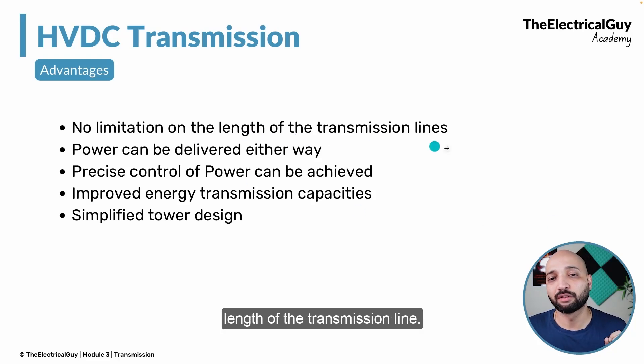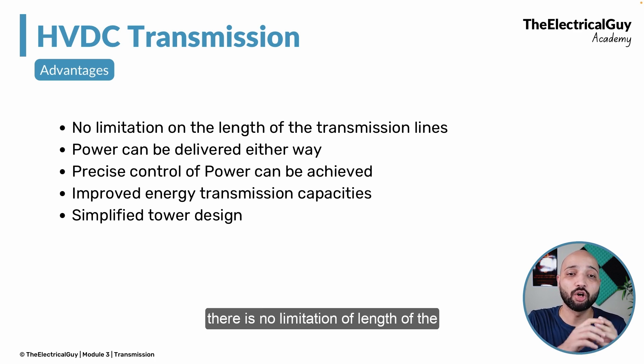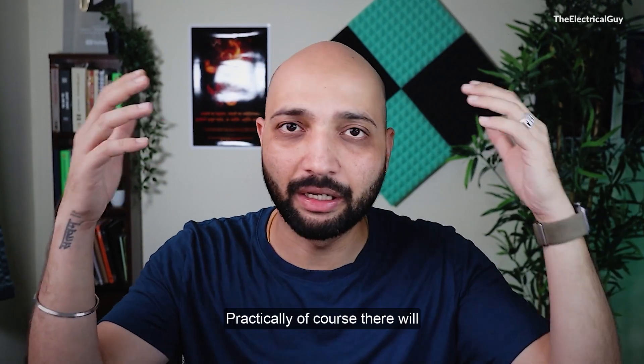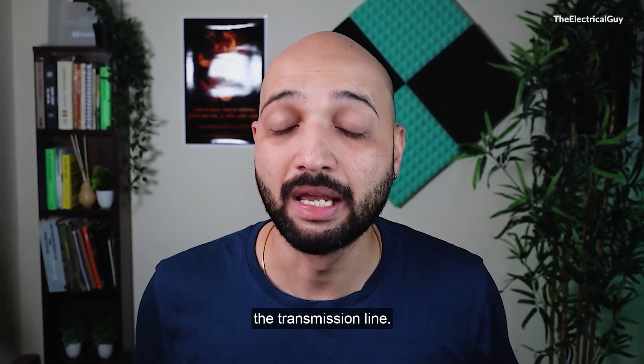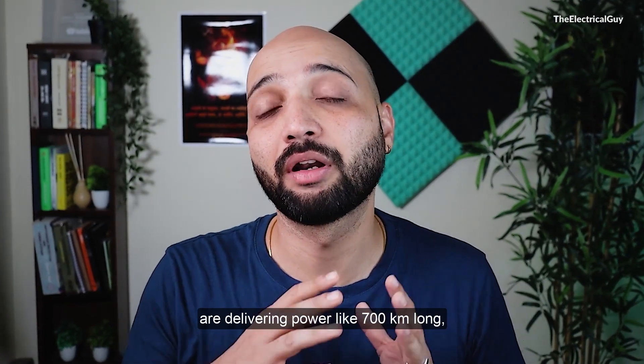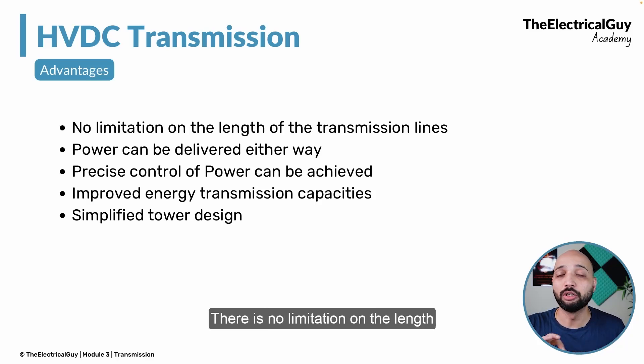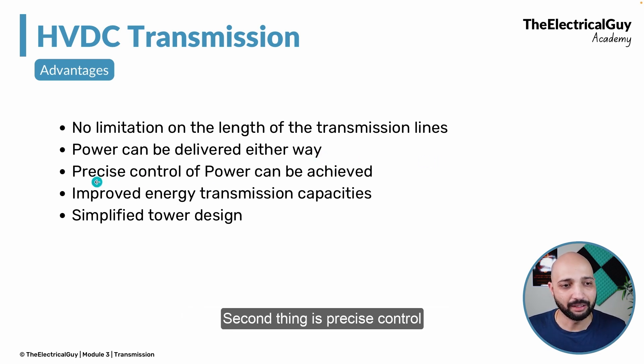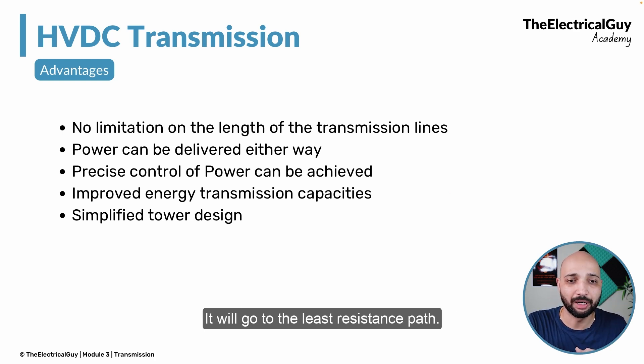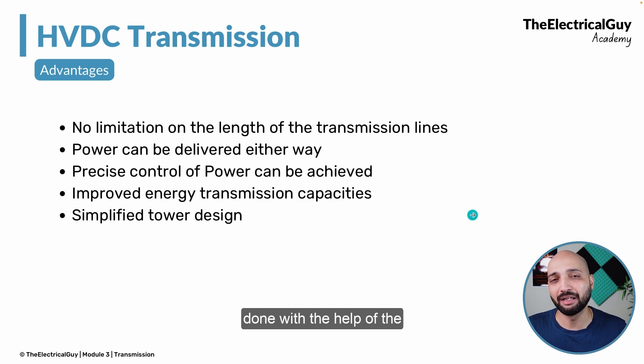The first advantage of HVDC is no limitation on the length of the transmission line. Since we eliminate the inductive and capacitive elements in DC, there is ideally no limitation on transmission length. There are already projects delivering power over 700, 800, even 1000 kilometers. The second advantage is that power can be transmitted either way. Third, precise control of power can be achieved — unlike AC where power flows to the path of least resistance, DC offers greater control through the converter stations.